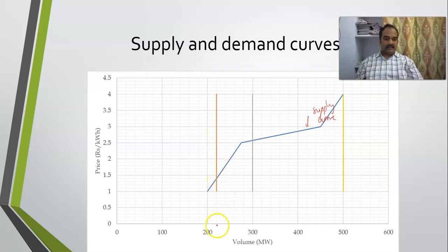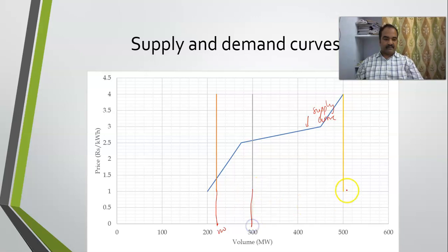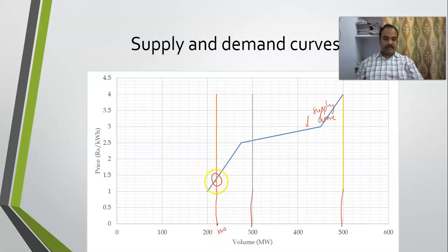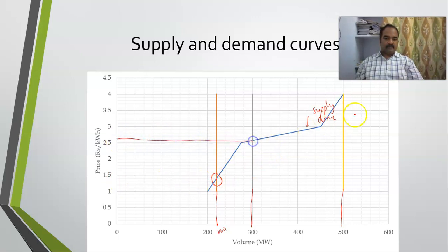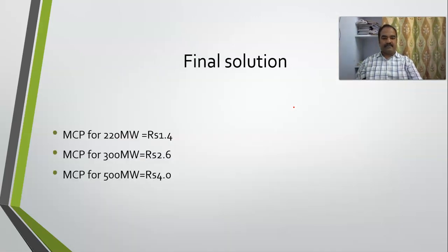Once the supply curve is drawn, I have different forecasts of demand. If demand is 220 megawatts, I mark this point at 220 and draw a vertical line — this is my 220 MW line. Similarly for 300 MW and 500 MW. The intersection of these lines with the supply curve gives the MCP: if forecasted demand is 220 MW, MCP is around 1.4; if 300 MW, MCP is around 2.6; if 500 MW, MCP is around 4.